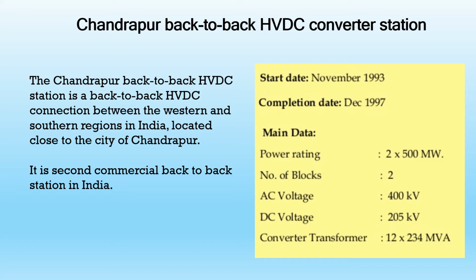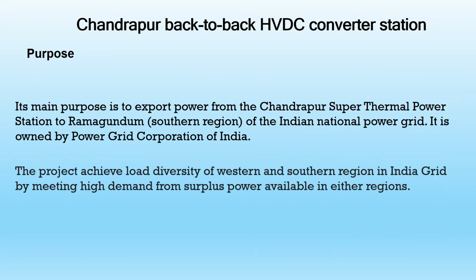The converter station consists of two independent poles, each with a nominal power transmission rating of 500 MW. Both poles were built by GEC Alstom between 1993 and 1997 and have a nominal DC and AC voltage of 205 kV and 400 kV respectively. Its main purpose is to export power from Chandrapur Super Thermal Power Station to Ramagundam of India National Power Grid. It is owned by Power Grid Corporation of India Limited.